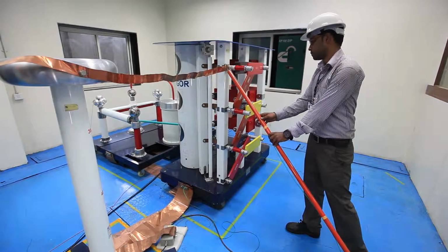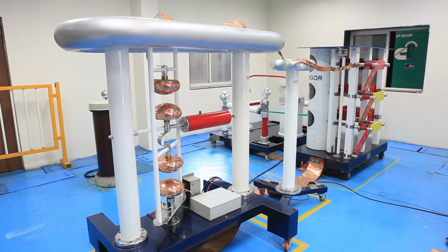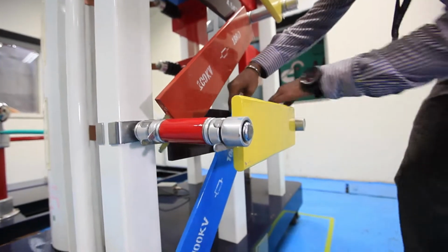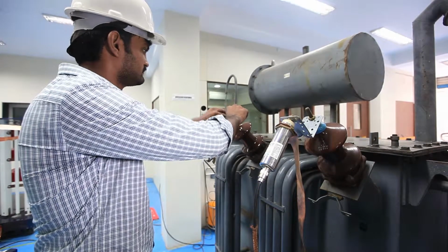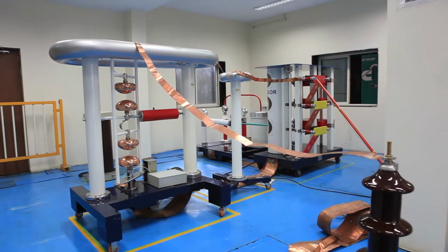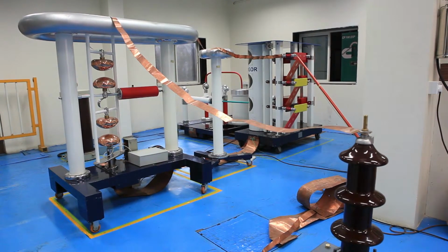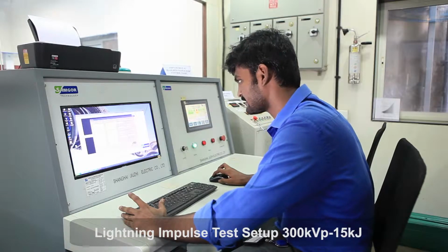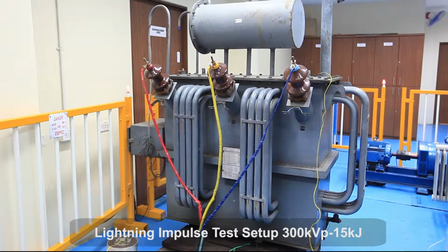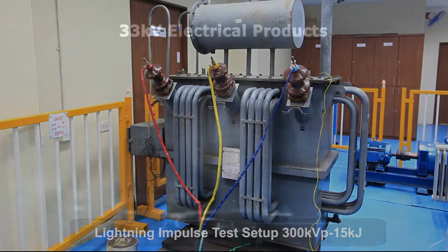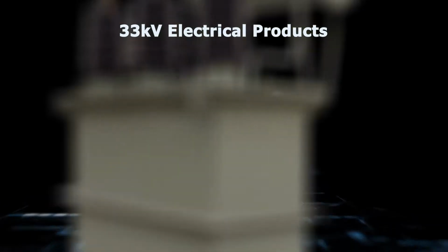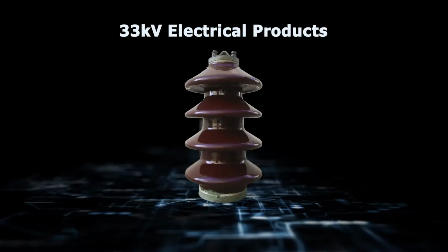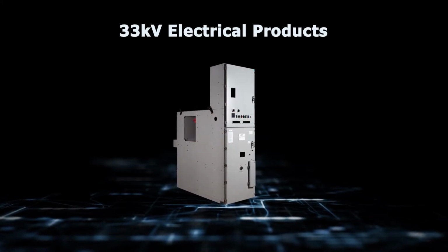ERDA West has set up a high voltage impulse laboratory with a capacity of 300 kV peak, 15 kilojoules. This state-of-the-art impulse test laboratory conducts lightning impulse test on a large variety of 33 kV electrical products, including distribution transformers, instrument transformers, reactors, insulators, bushings, panels, and so on.